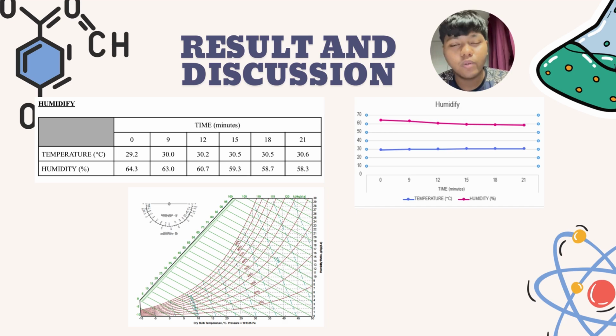So next we move on to the humidifying part of our experiment. Looking at our temperature data, we can see that our temperature is slightly increasing from 29.2 degrees Celsius to 30.6 degrees Celsius. So this small rise suggests that moisture addition adds a minor amount of heat. In this case, it can be the latent heat of vaporization. For our humidity data, the humidity decreased from 64.3% to 58.3%.